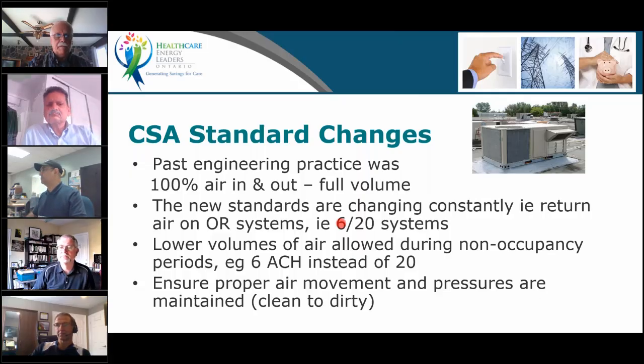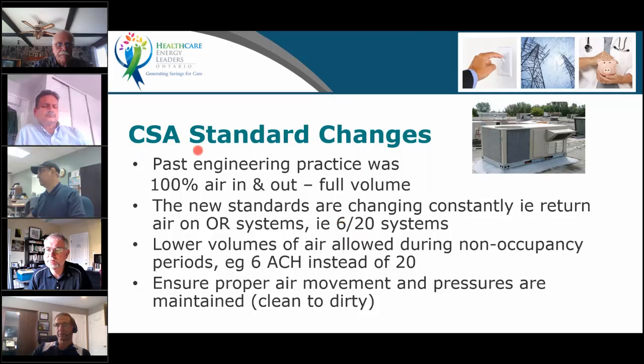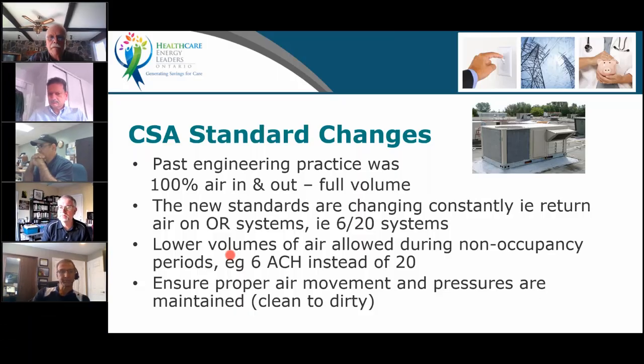So if you are running 100% fresh air, you're using an older version of what the CSA standard was. And if it's possible, and you can go to something like a 6/20, then you can achieve some significant savings. And like I said before, CSA also allows you to go to lower volumes, and for some spaces you can actually stop the system. So you have to always be on top of that. Where can I stop it? When I stop it, do I have to monitor the space or not? So make sure you're aware of that.